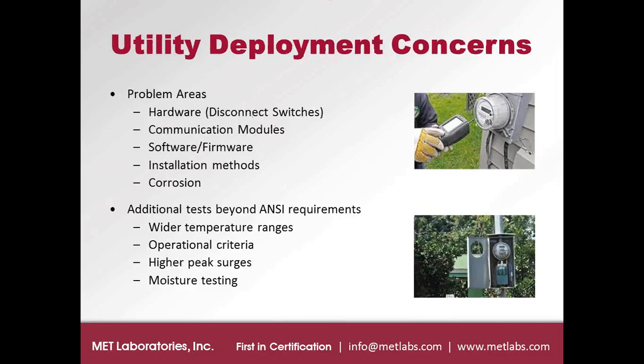Utility concerns. Again, this could be manufacturers as well, but problems that you're seeing in the field, things that we could develop tests for here that would go beyond what's in ANSI: wider temperature ranges, longer durations, anything that the manufacturer or a utility may come to us and talk about seeing in the field. We would try to develop a test program here to simulate those events that they're seeing in the field and try to uncover what the problem may be. We certainly can help you with a test program such as that.